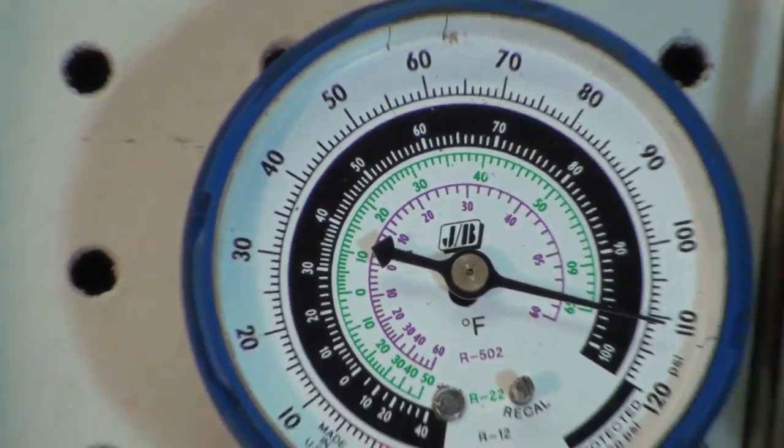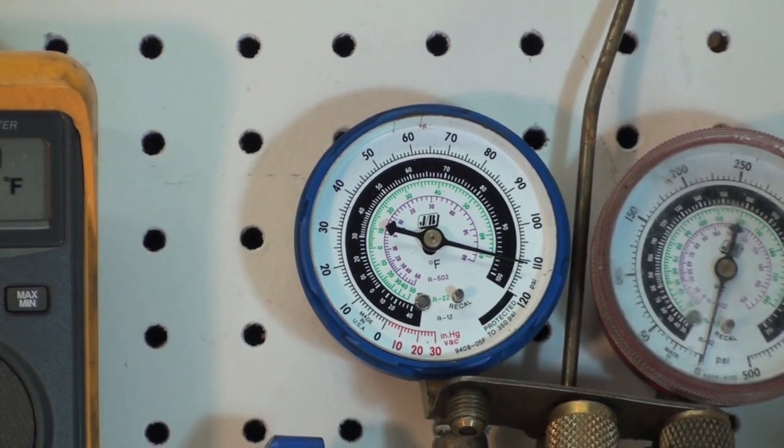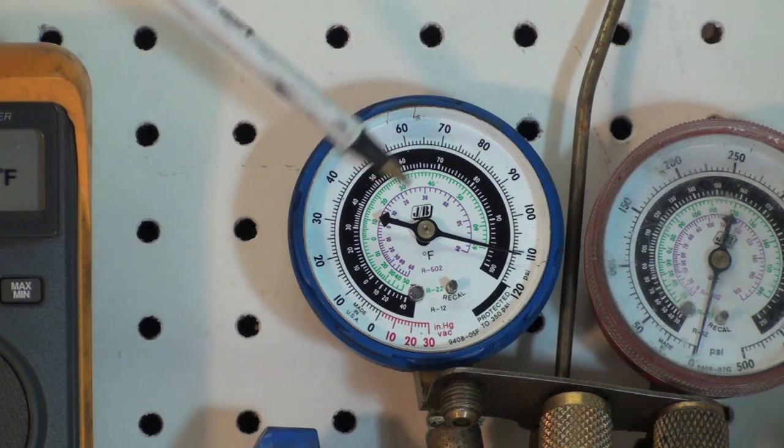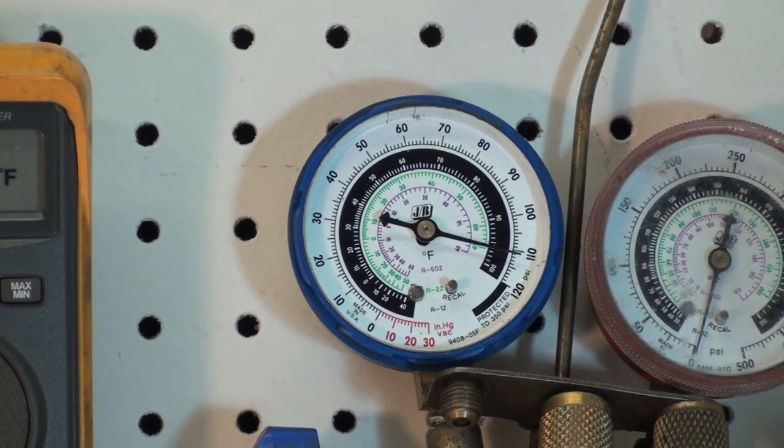The gauges that we use, these manifold gauge sets, are set up with several different refrigerants on the scale like R12, 502, and 22 on this one. This is an old scale. We're still using 22, but 502 and 12 are pretty much gone. But you can see that temperature equals pressure. Now there are charts for this, pressure-temperature charts, and on the Great Cooling Man website I have those links to them and there's an app and a bunch of stuff like that. You can get them all over the internet and they will show you what the different pressures will be for the different refrigerants.